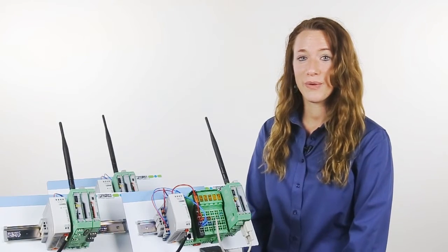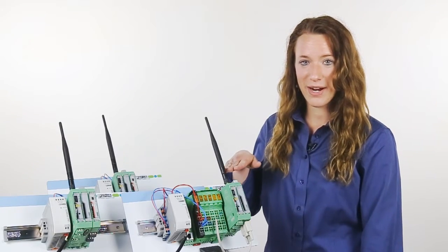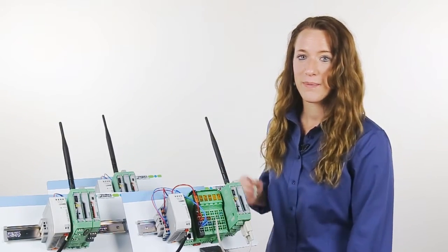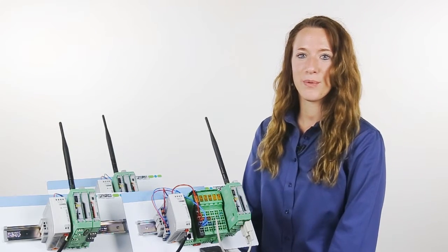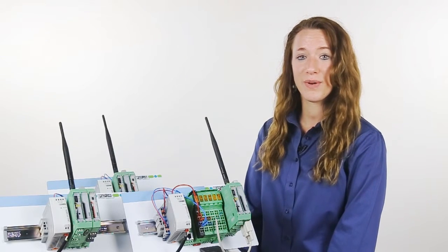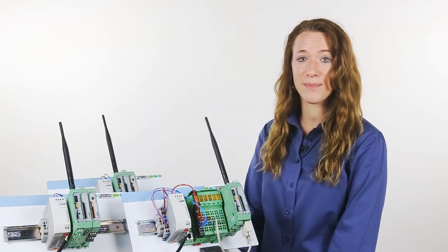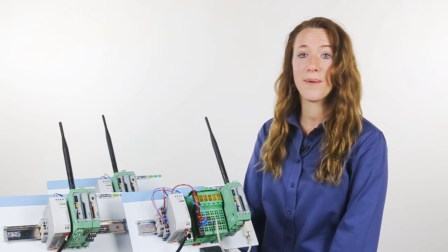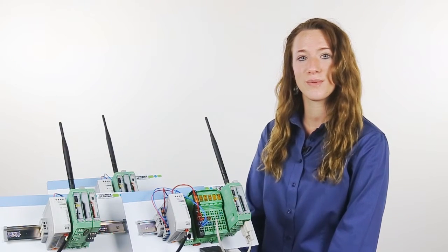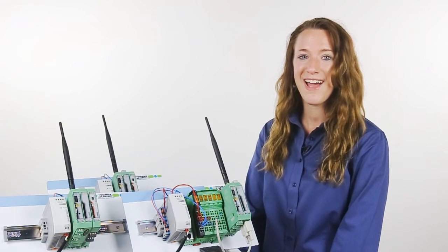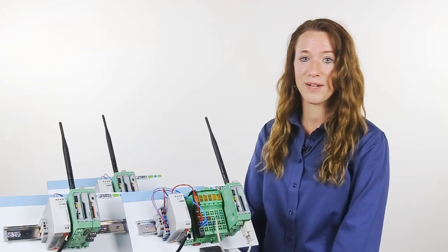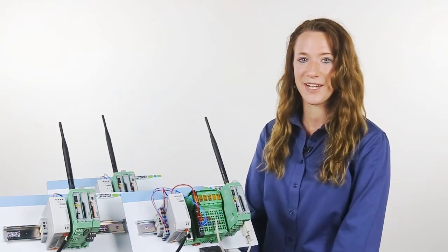This video is going to show you how to quickly program the Radioline wireless system for PLC mode. In this setup, you will configure two Radioline wireless modules with expandable I/O as repeater slaves that will communicate to a Radioline wireless master module acting as a Modbus RTU gateway to a PLC.